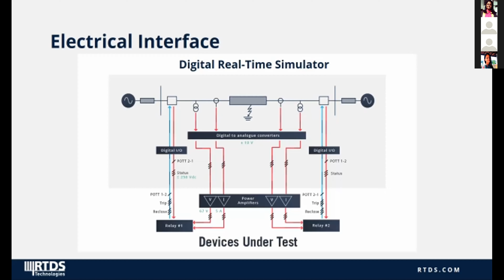Here, the output contacts from the physical relays are used as input signals to control the simulator's circuit breakers. Relay trip commands are sent to the simulator using the digital input card. The digital output card is used to communicate circuit breaker statuses to the physical relays. In this way, we can create a closed loop between the digital real-time simulator and protection relays.